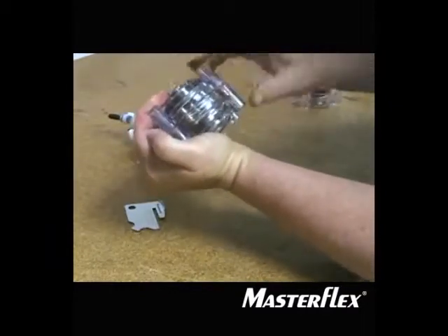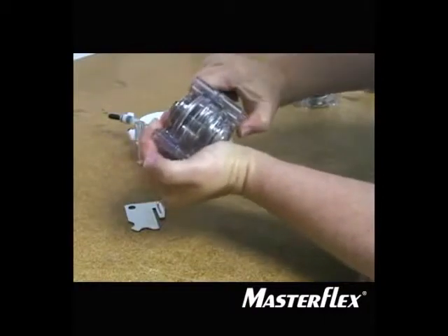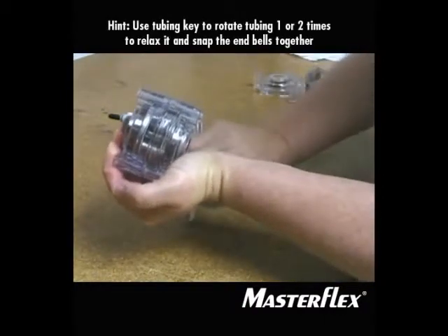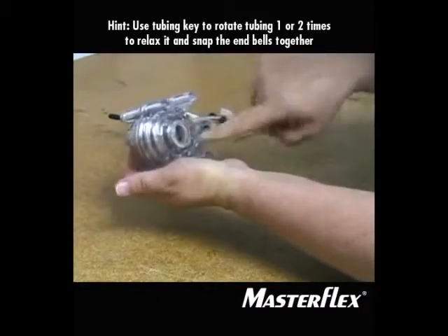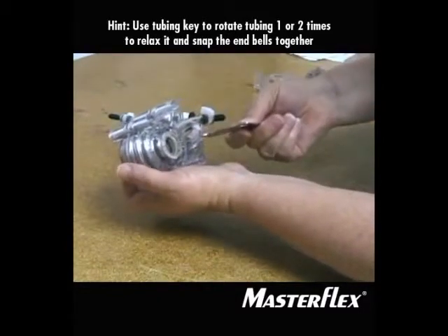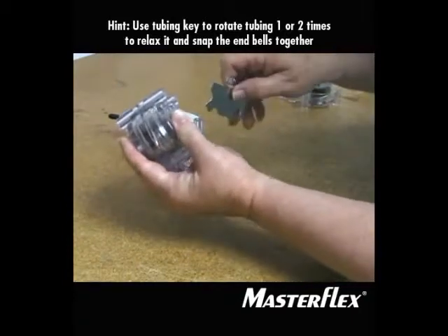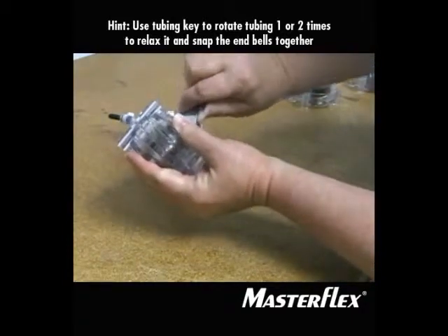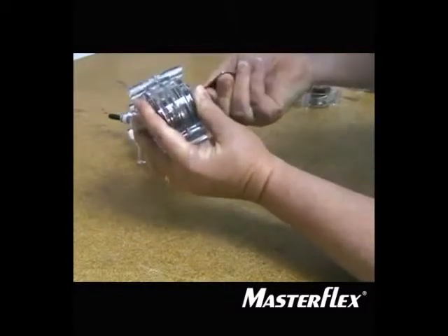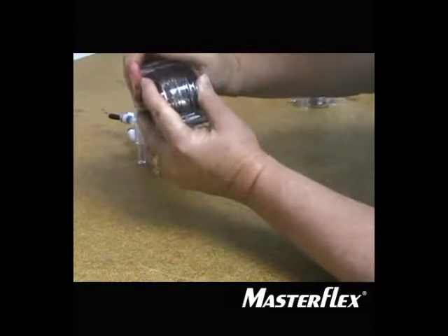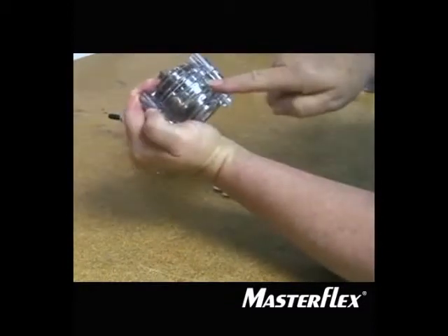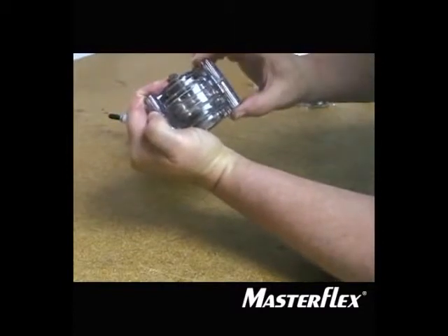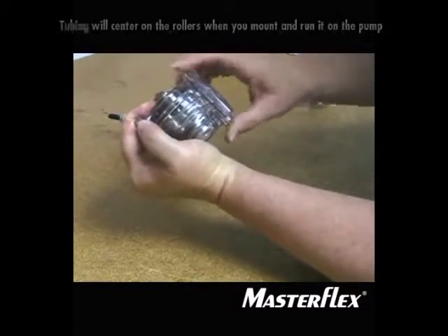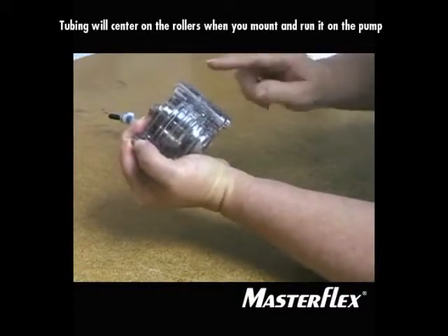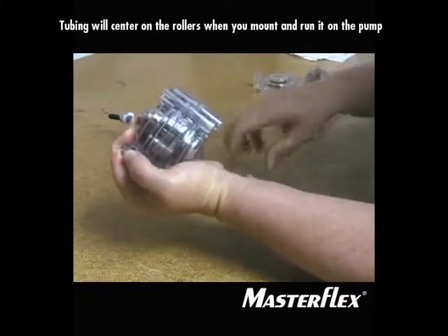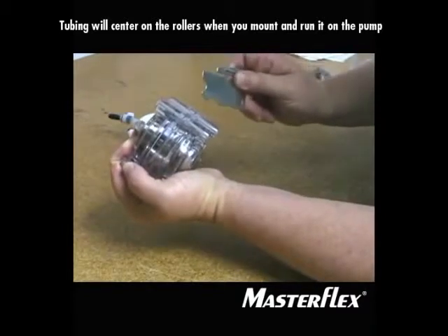Now sometimes when you're trying to put the pump together, it's just a little bit difficult. So take the key once again. And I'm going to put it in the slot. And I'm going to turn it one or two rotations. This will stretch the tubing a little bit and relax it. And then I'll be able to close the pump a little bit easier. There it goes. Now, making sure you don't pinch the tube and seeing that it is centered. If it's not quite all the way centered, don't worry. Because once you mount it on the drive and you run it, it will automatically center inside the pump because you've used the key and you've stretched the tube properly.